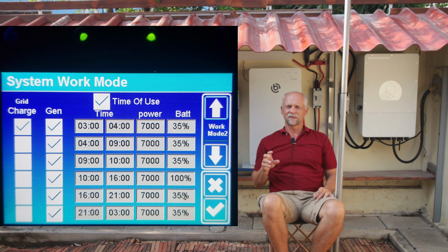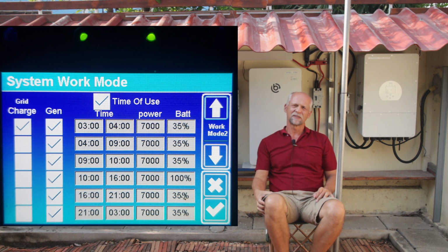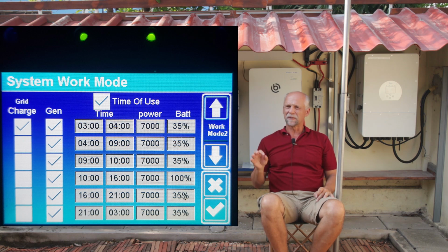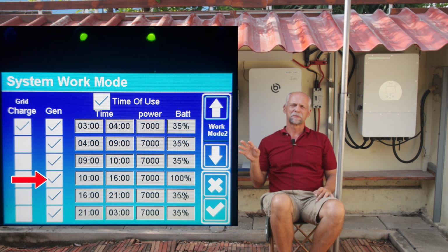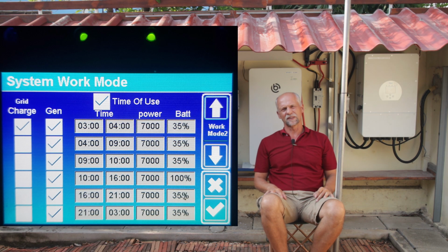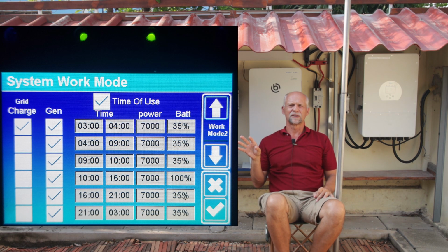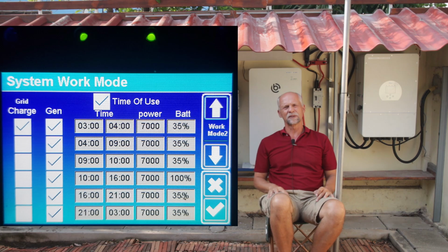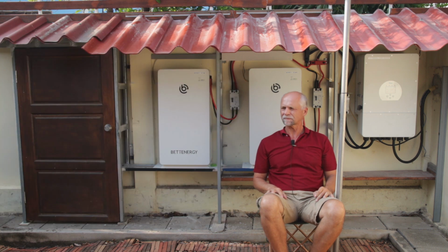So I make sure I have a period in the table where I demand the battery state of charge, if energy is available from the PV system, tries to reach at least 100%. And it's good to remain at that full state of charge for at least 30 minutes to an hour at the end of the day, to give the balancer time to do its job.